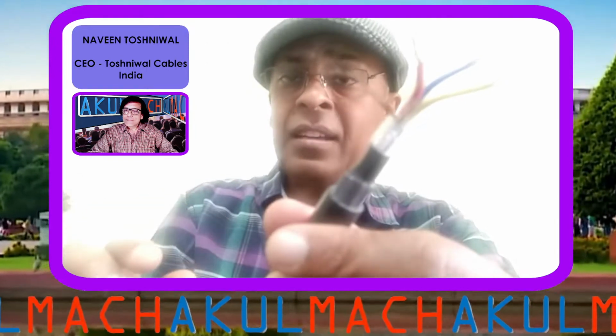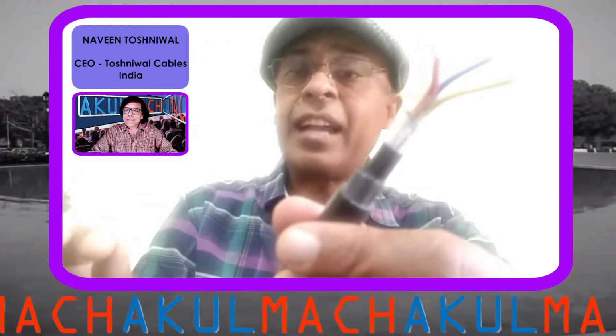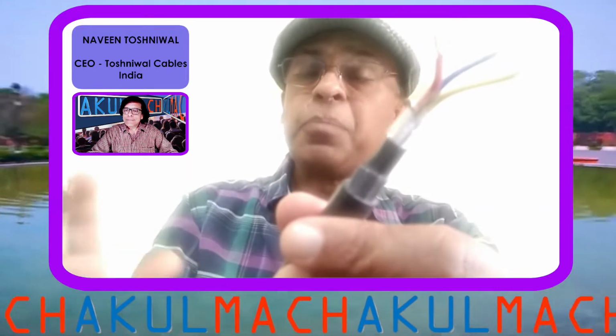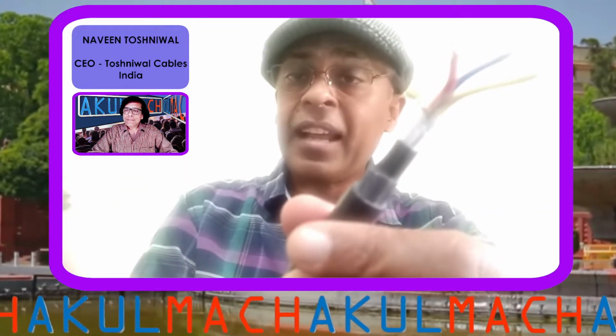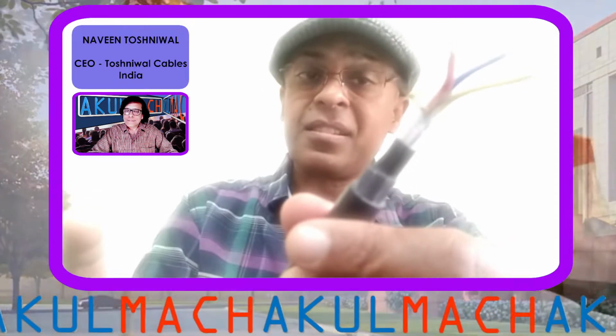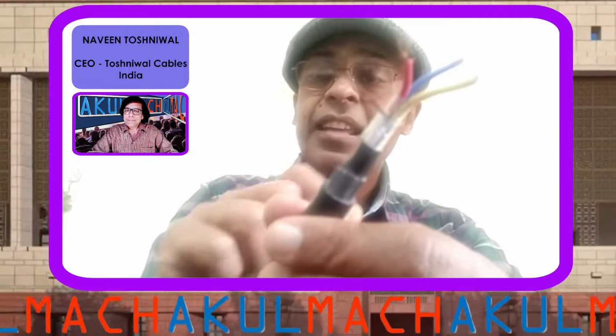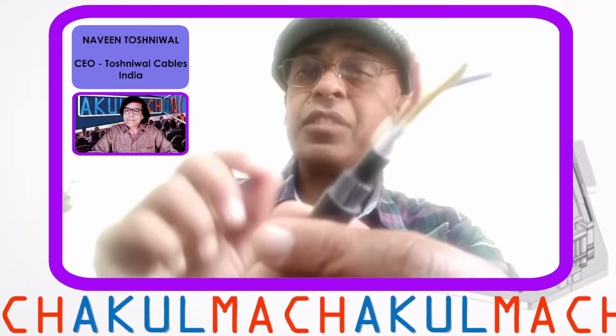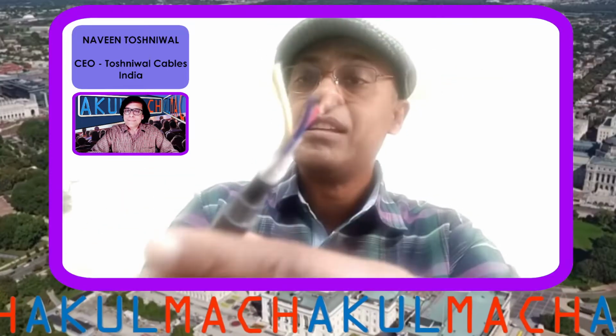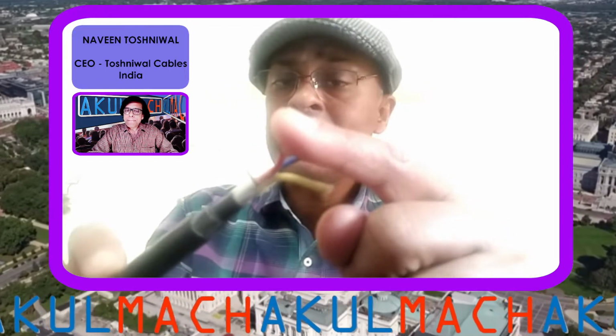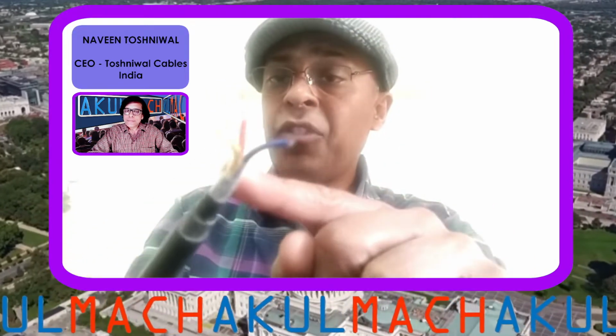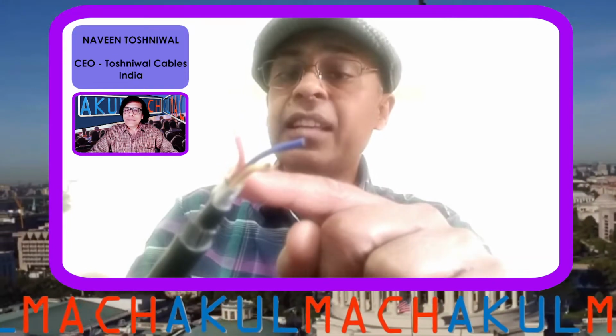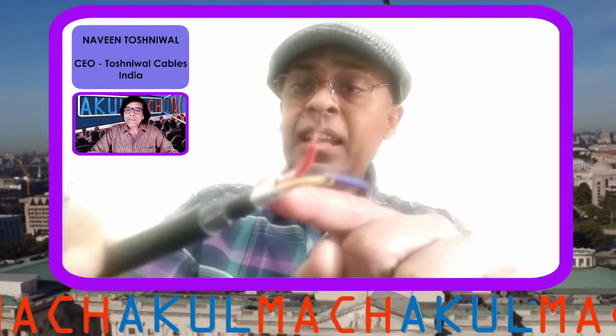The purpose of this is to prevent or reduce the electrostatic interference which may come from nearby electrical or high voltage or high current cables, because any such interference will distort the signal going inside this RTD cable. So this shielding is a must for these specialized cables which carry very few millivolts. So this is a three-core cable, as I said, with a shielding for reducing electrostatic interference. Then there is another feature you will see.